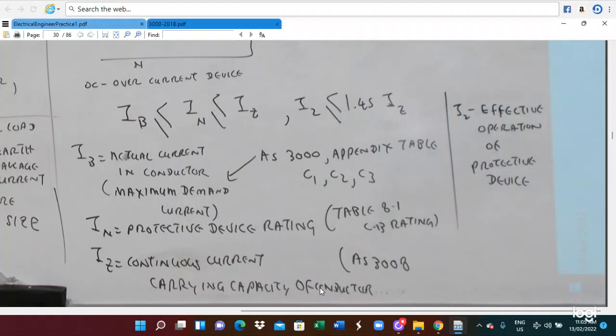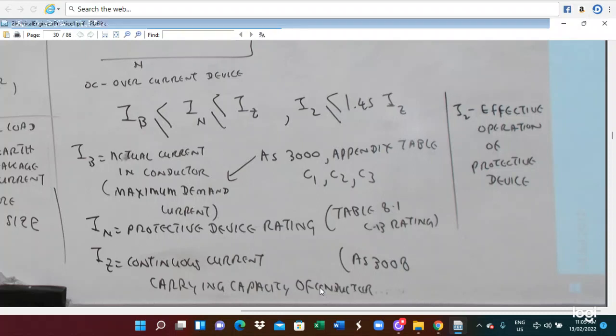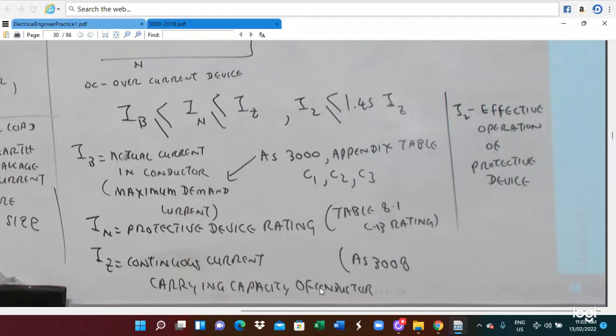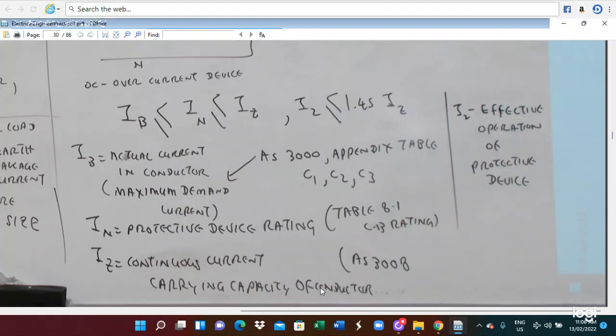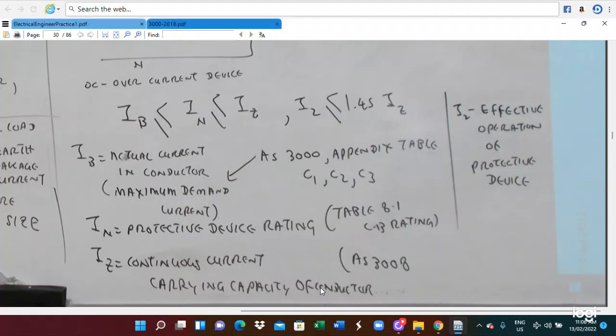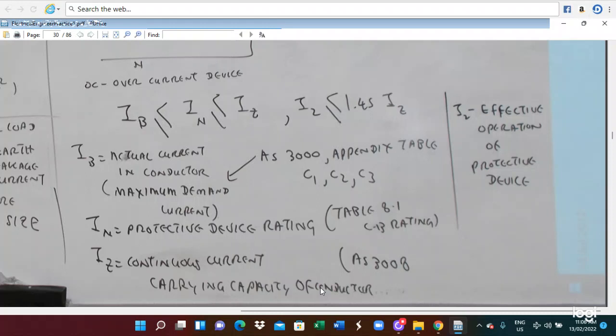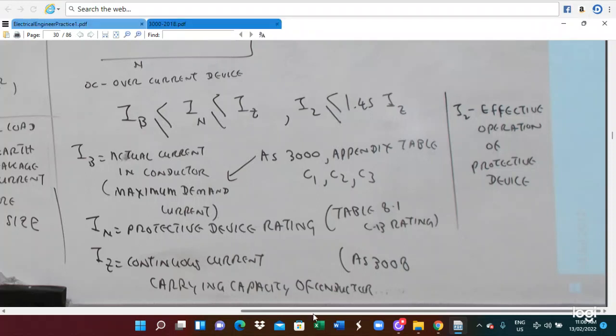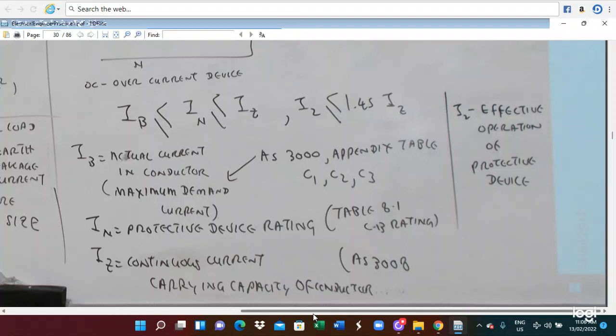Now I am talking to you about how to arrange the whole system, the current, the equipment: how to set the protective devices, how to configure them with your supply conductor, and also how to select your cable size. I am giving you the overview picture. There are three currents in the electrical installation you have to be aware of. IB is the actual current in the conductor.